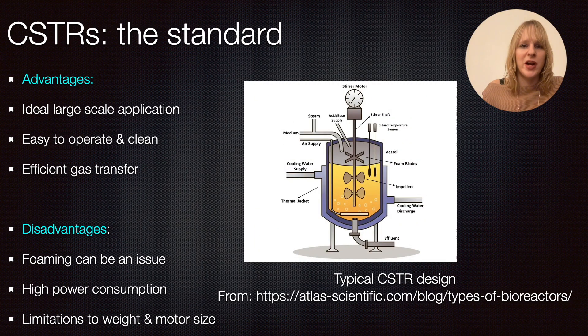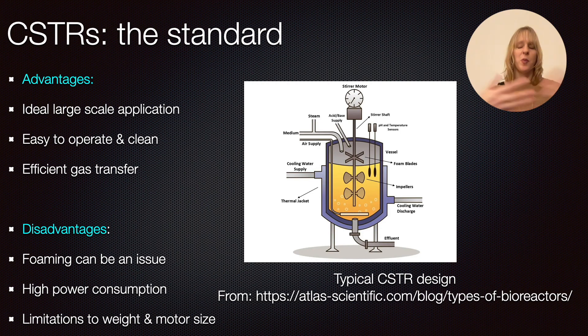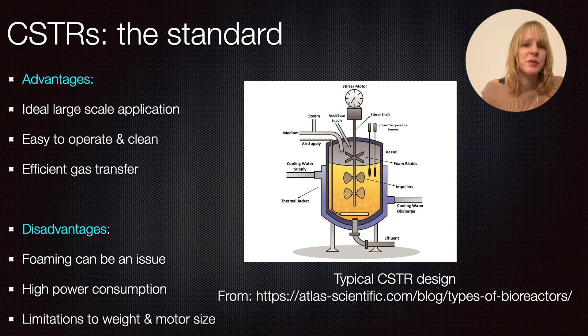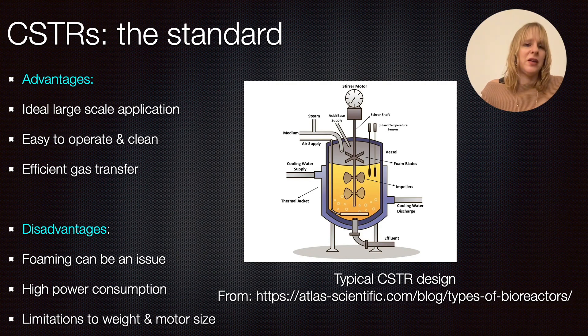The most common stirred tank bioreactor is the continuous stirred tank reactor. Continuous operation has several advantages: it's ideal for large-scale applications, very easy to operate under steady state, and can run for a very prolonged period of time. It's easy to clean and allows very efficient gas transfer. However, foaming is always considered a major issue, so one of the standard sensors you'll need is an on-off sensor that detects foaming and triggers addition of an antifoaming agent.